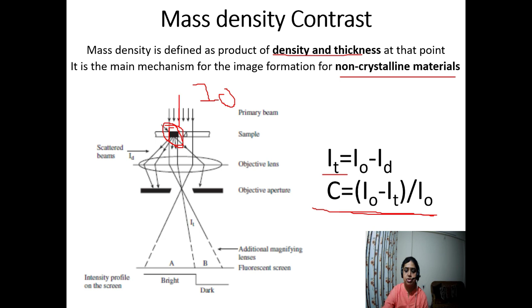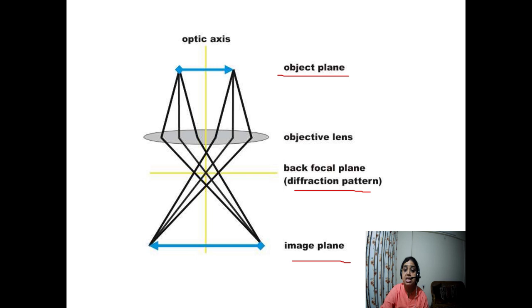Basically, mass density is defined as the product of density and thickness at a point. Suppose you want to take an image over here; it is defined by the density of the material and the thickness there. This is the main mechanism for the formation of the TEM image in amorphous solids. Now let's come to the optical path. This is your optic axis, this is your objective lens, this is the object plane, and this is your image plane. There is one very important plane, the back focal plane, or diffraction plane. This is the plane from where we can get structural information about the material. It is used for structural analysis.